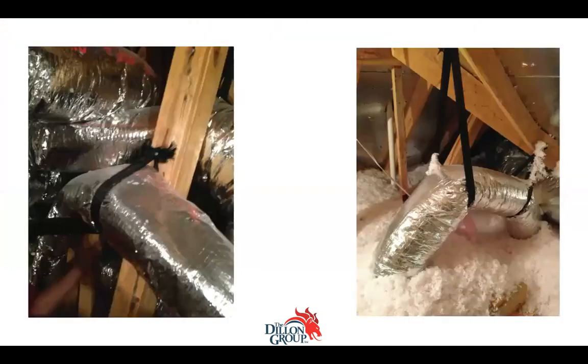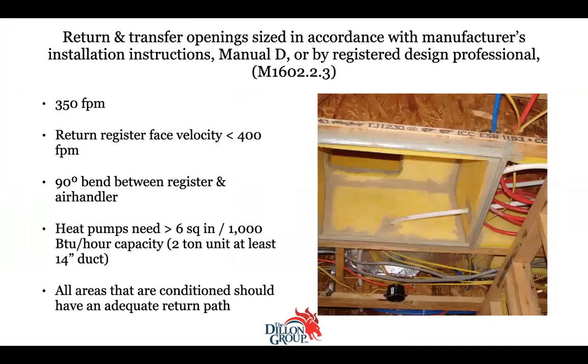I mean, I could go on and on. I won't. You guys have been out in the field. You've seen the damage. How about this one? Return and transfer openings have to be sized in accordance with manufacturer's installation instructions, Manual D, or a registered design professional. So here are some general rules that come out of Manual D for return grills and returns in general.